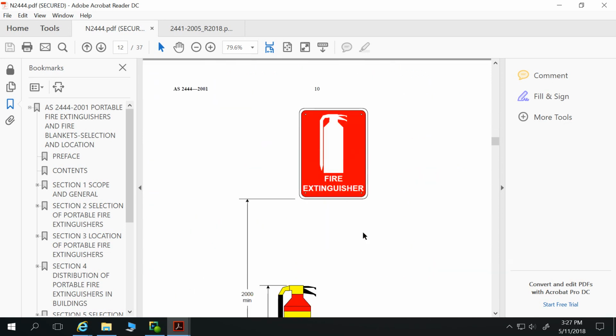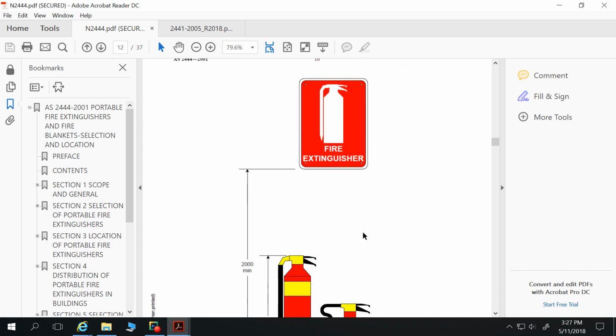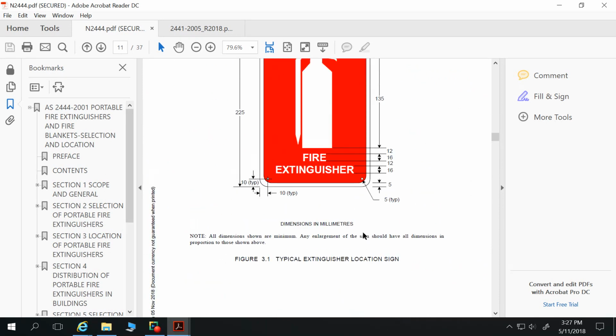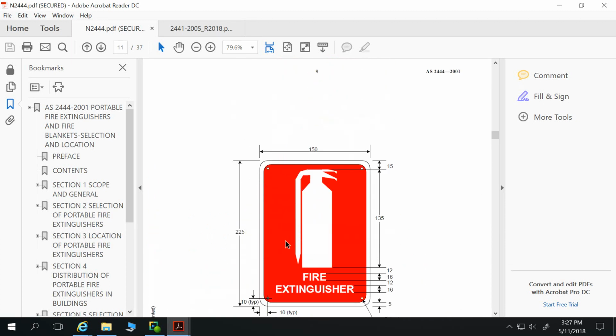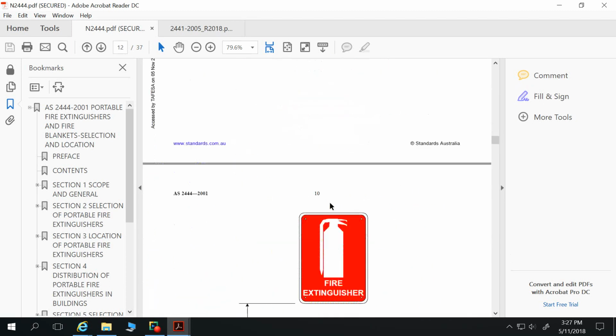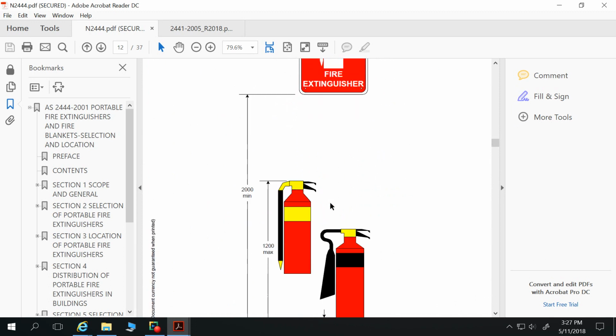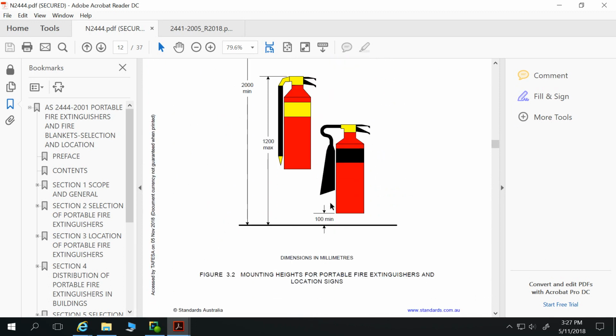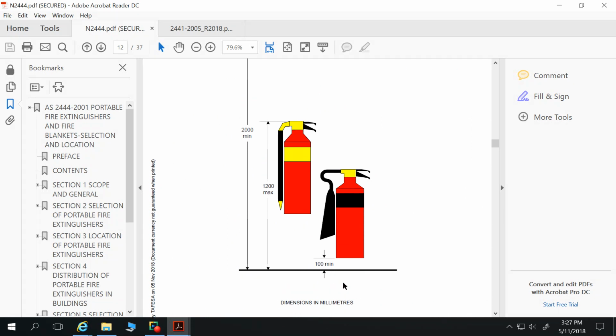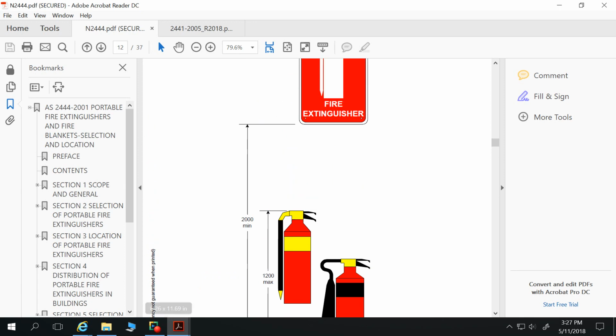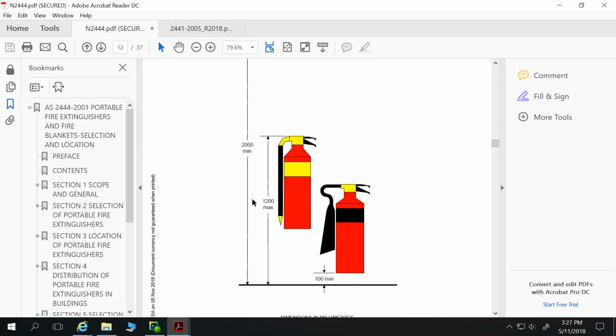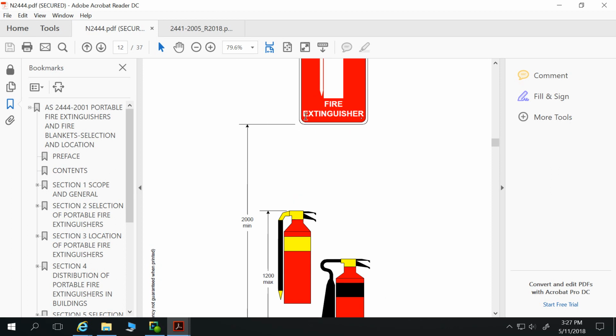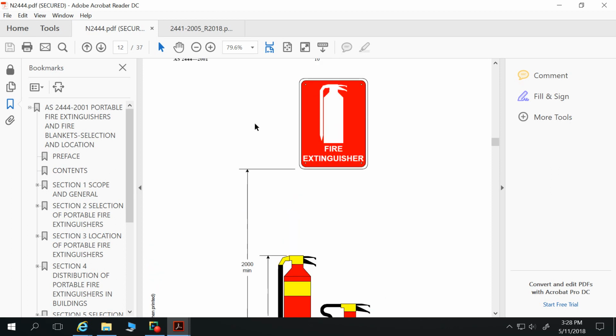So, our typical extinguisher location sign. We have a sign like that, and our mounting heights. So, mounting heights of portable fire extinguishers and location signs: at least 100 millimetres off the ground, but a maximum of 1200, so somewhere in that Goldilocks zone. And then our fire extinguisher sign, minimum 2 metres from the floor.